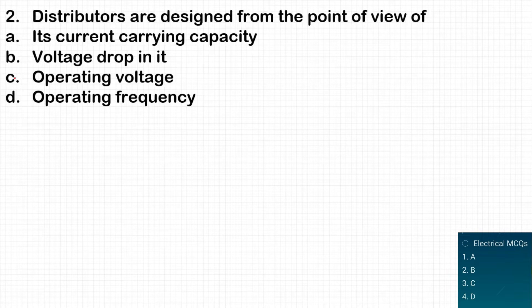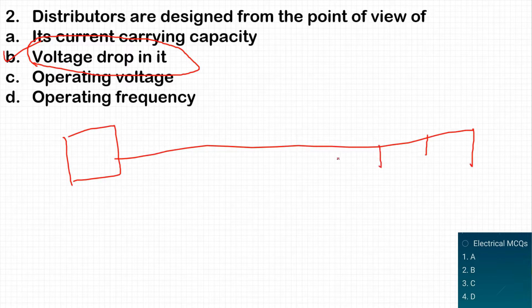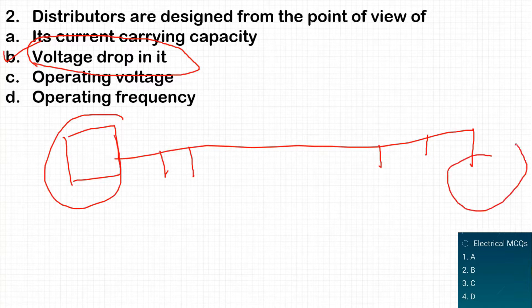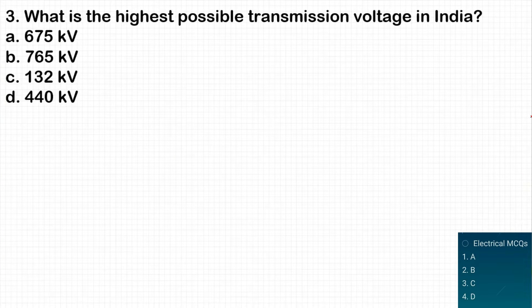The next question: distributors are designed from the point of view of which parameter? Unlike the feeder, distributors are designed from the point of view of voltage drop, because distributors supply current to consumers and all consumers must have the same voltage. We must consider the voltage drop in the distributor to assure all consumers have the same voltage at the point of supply.